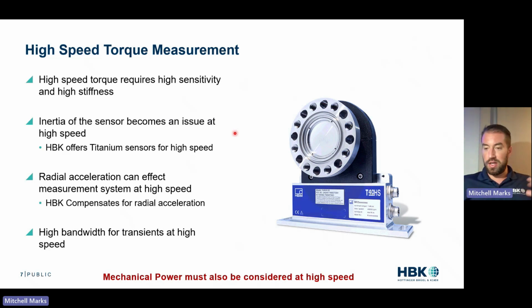I'm an electrical engineer by nature, so springs are a little bit of a mystery to me, but you end up with this spring issue. So HBK does offer titanium sensors that go up to 45,000 RPM. We actually have a high speed series. Because this is quite difficult, we go to a different material, titanium, to lower that inertia and get that stiffness but sensitivity. There's also the issue that at high speed, most torque sensors are strain based.